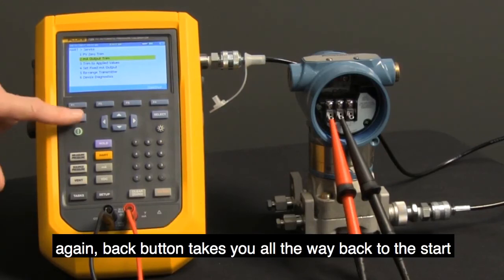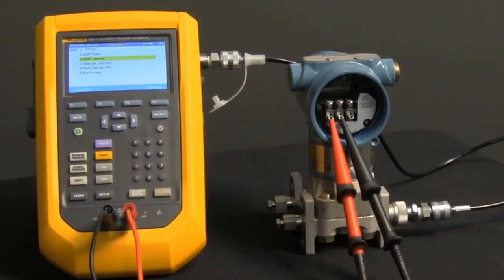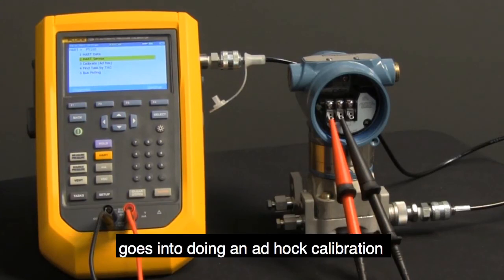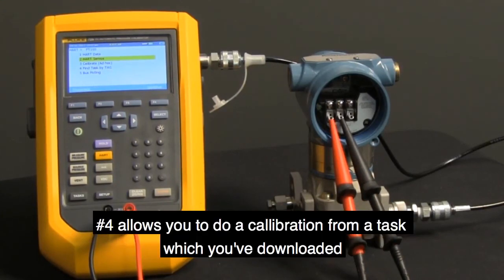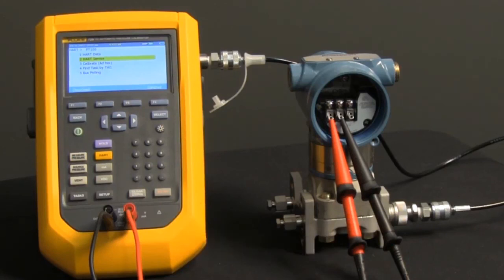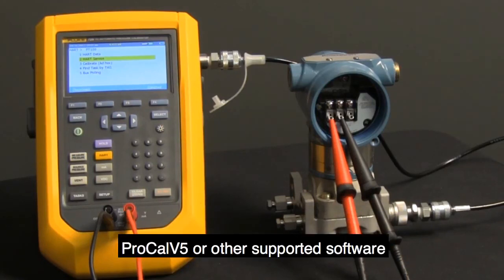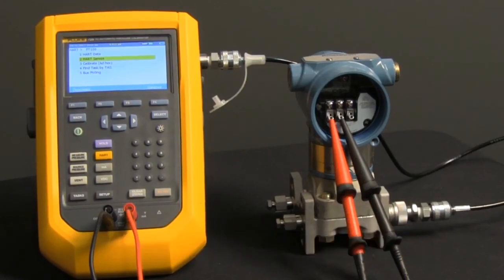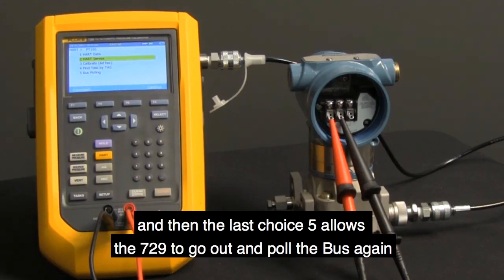Again, the back button takes me right back to the start. Choice number 3 goes into doing an ad hoc calibration. Number 4 allows you to do a calibration from a task which you've downloaded from DPC Track 2, ProCal V5, or another supported software. The last choice, 5, allows the 729 to go out and poll the bus again.